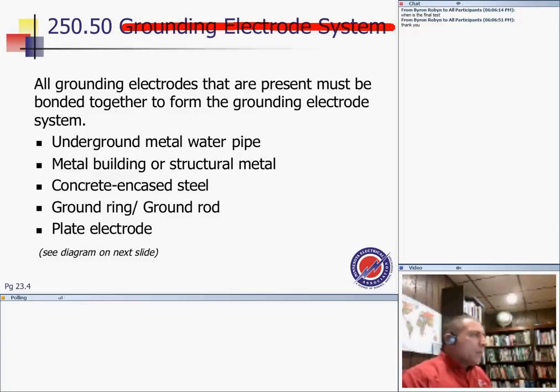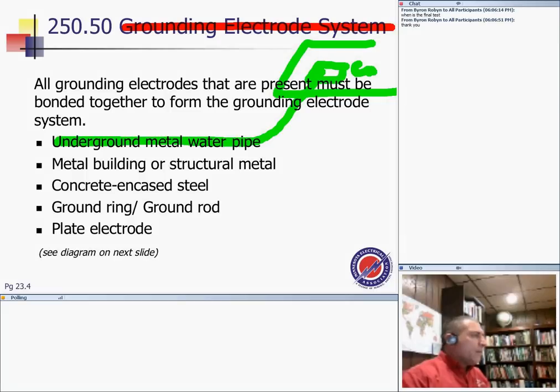So by code, you have to have at least one grounding electrode system. And the code, 250.50, clarifies what systems qualify as the grounding electrode system. Here's one of them. It's an underground metal water pipe that you can tie your grounding electrode conductor to, and tie it to the ground bar in the panel. That could qualify. Or you can tie it to the metal building or the structural metal, with some requirements that you have to do. Or you can do the concrete encased steel. You have rebars or steel bars in a concrete encased cover, and these are in direct contact with Mother Earth. These guys can qualify as a grounding electrode system.